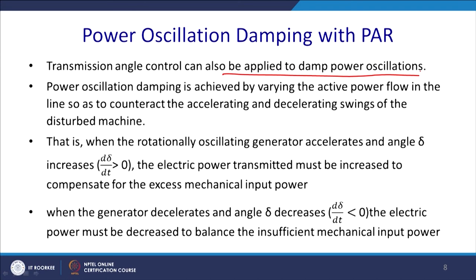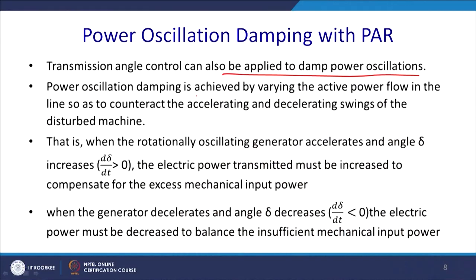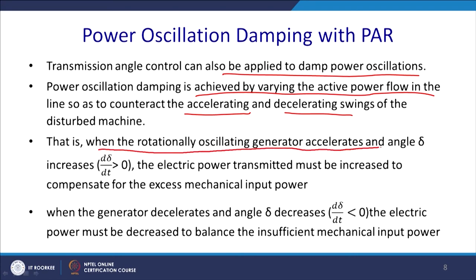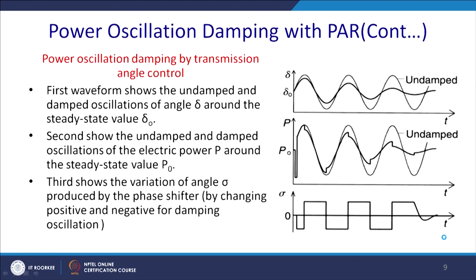We have seen it in the case of the series, in the case of the shunt, and it is also applicable for the power angle regulator. The power oscillation damping is achieved by varying the active power flow in the line, so as to counteract the accelerating and the decelerating swing of the disturbed machines or line. When the oscillating generator's angle delta increases, d delta by dt is greater than 0, that means you have an acceleration. The electric power transmitted must be increased to compensate the excess mechanical power. When the generator decelerates, the angle decreases and the electric power must be decreased to balance the insufficient mechanical input power. So, this is the case.